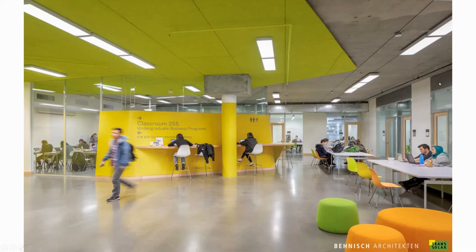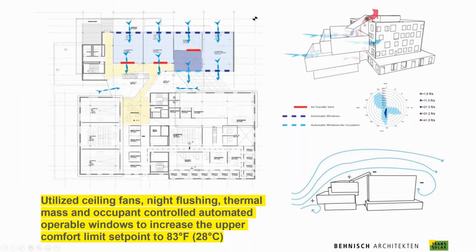Above the classrooms are acoustically protected vents between the classrooms and the corridor — critical components that are always the hardest to design because in order to be acoustically protective, they need a lot of acoustic baffles, which fill up the space and limit free area. These take the biggest mental hurdle to accept in terms of how much space they occupy. But the more free area you have in these, the less pressure drop and the more free-flowing the whole system is. On the top floor, the edge classroom uses cross ventilation rather than connecting to the atrium, which is not uncommon — some spaces have a different strategy based on their architectural configuration. A high space has more wind pressure driving natural ventilation through.